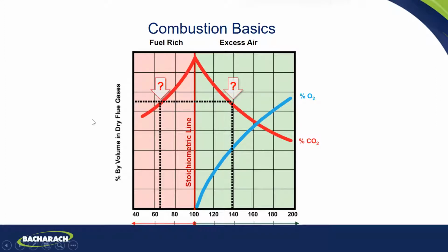So they brought in a boiler man who had Bacharach equipment. He went in, and every one of the boilers was running over here. He worked on them with the Bacharach equipment and had them brought over here, and they saved tens of thousands of dollars after that. There is another company that uses CO2, but they have to work out how they're going to determine their combustion efficiency. I think they do it CO2 to CO. So you should always know on the combustion analyzer, if it's not a Bacharach, which type of sensor you have when you're measuring combustion efficiency.